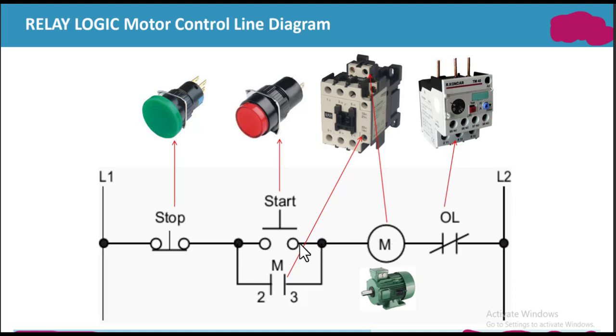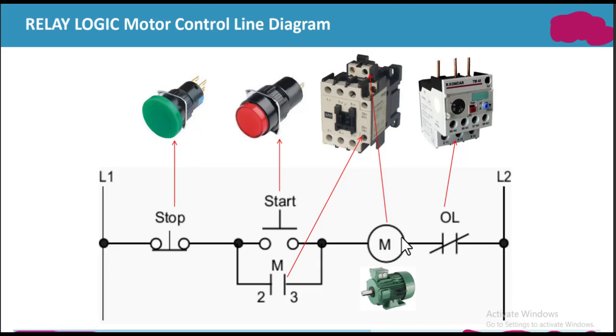When we release the start switch, the current can also pass through this alternate path to the motor. The start switch is just used to start the motor — it is a push button. When we release it, the current has an alternate path to flow to the motor, so the motor will remain in the running condition.